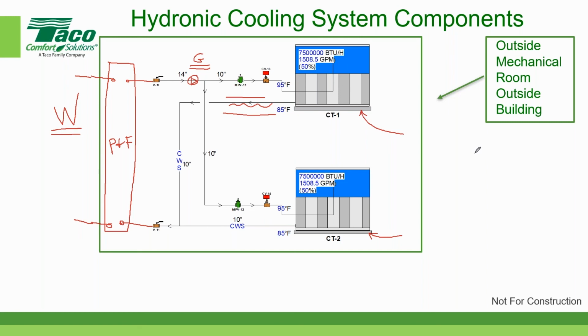Not many designs do I see, when I look at people's prints and review them, where people are running the glycol around the whole building. Usually they separate it with a plate and frame or some type of heat exchanger. Right. In Cranston, in the Innovation and Development Center, IDC building. Is that how you say it? ICD? IDC. IDC, yeah. Innovation Development Center. Yeah, our cooling towers run in the wintertime and they ice up, and we have basin heaters and we have heat trace and insulation on the piping. So yeah, we run our cooling towers 24 hours a day, 7 days a week, 365 days a year.